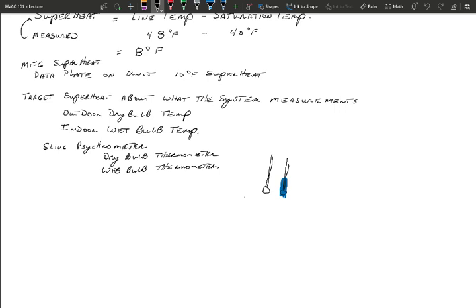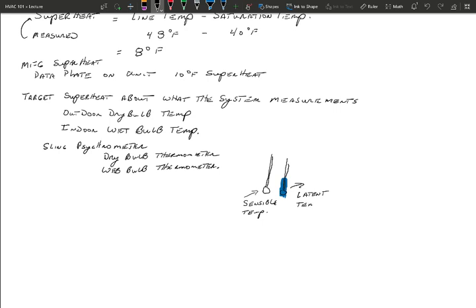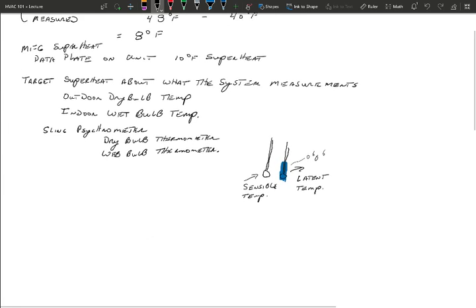It has on it a dry bulb thermometer and a wet bulb. We use the dry bulb outside. Here's a bulb and there's our thermometer. And then the other one is a bulb with a bulb at the bottom. But on this one we place a wick over top of all this, basically a little white sock that gets wet. As the air passes across the dry bulb, that reads the sensible temperature. And as air passes across this one, this reads the latent temperature. We will spend some time in lab playing with these devices.